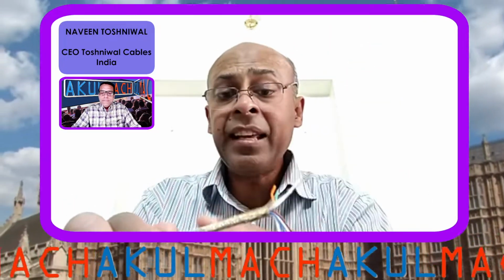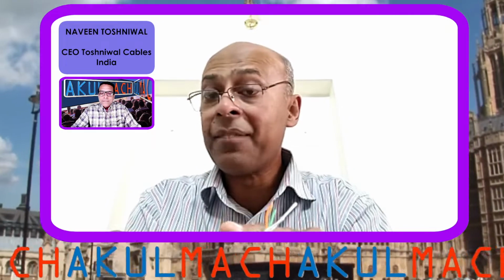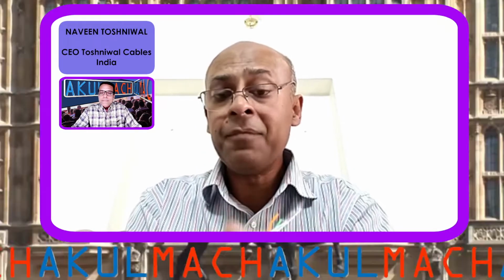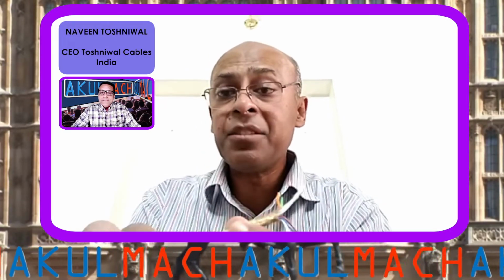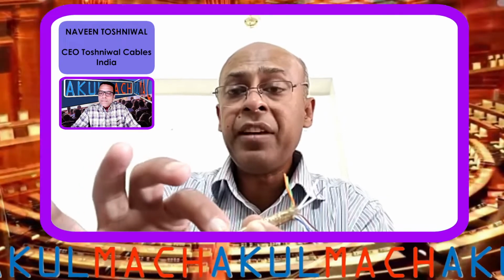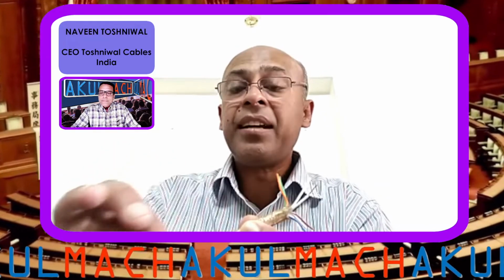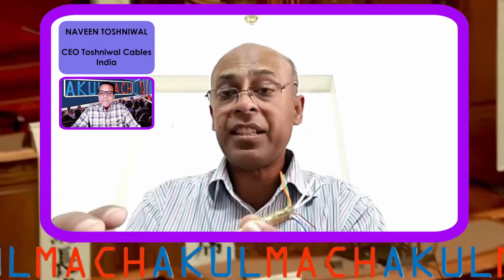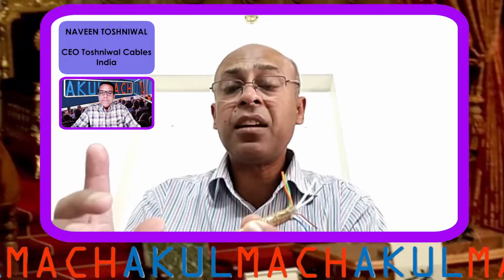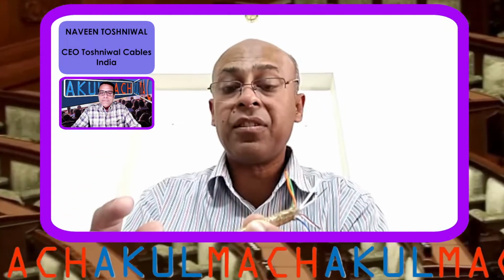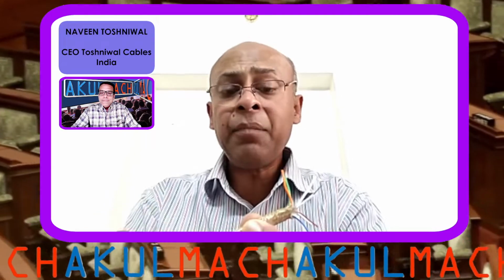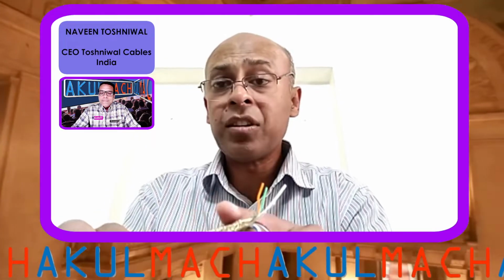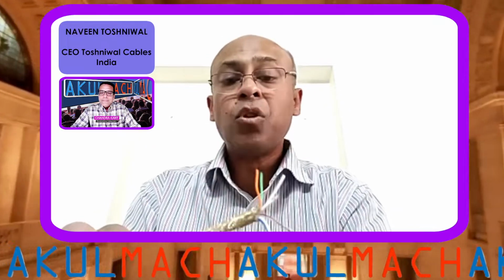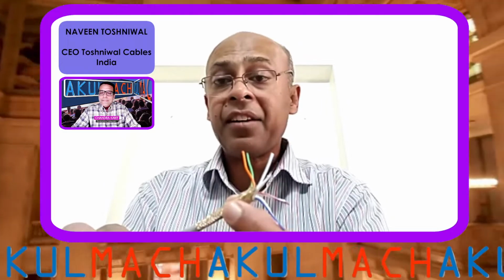Now shielding is of silver plating braiding. It is not tin copper. Silver plating is required in this case because when we apply the Teflon on the outer sheath, it has to go through a sintering process where high temperature of about 400 degrees is involved. In the sintering process, if tin is used on the braiding, the tinning will melt. So we have to go in for a higher grade, which is silver plated copper.